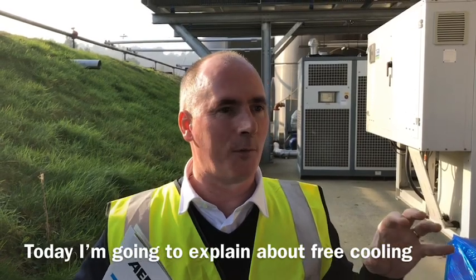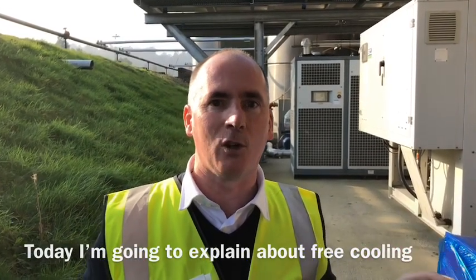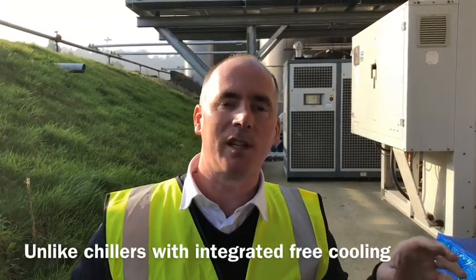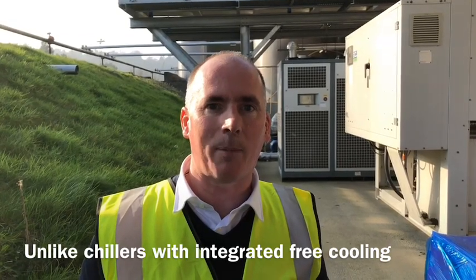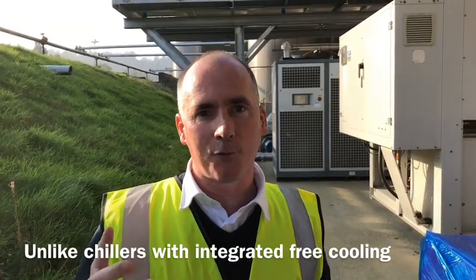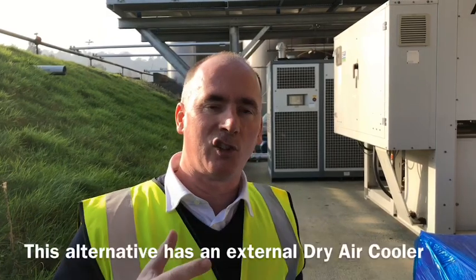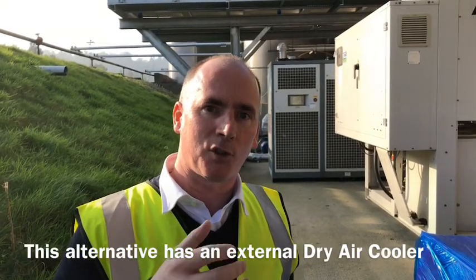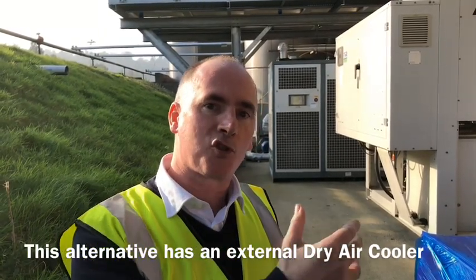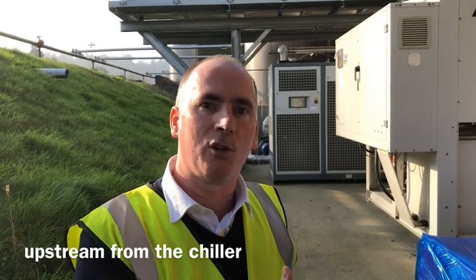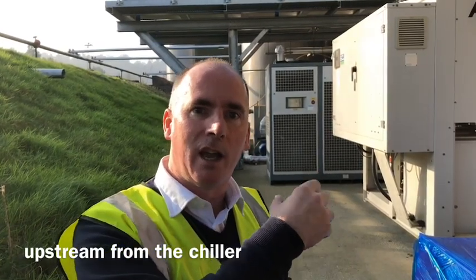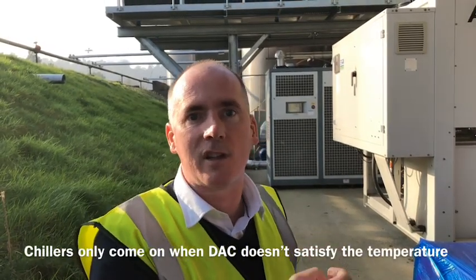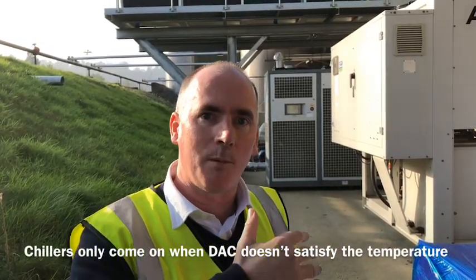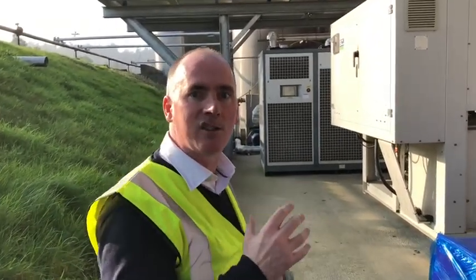The logic of what we're doing here today is to explain about free cooling. Some of you will have seen my vlog I've done from the Central Bank of Ireland, where we have free cooling built into the chillers. This is the other possible way of doing it, where we have a chiller and a Dry Air Cooler upstream. So the Dry Air Cooler does the free cooling first, and then the water, if it's cooled, it's satisfied, the chillers stay off automatically. If it's not, the chillers kick in automatically and make up the balance of the load. So I'll just show you around here just to give you an idea how it's all installed.